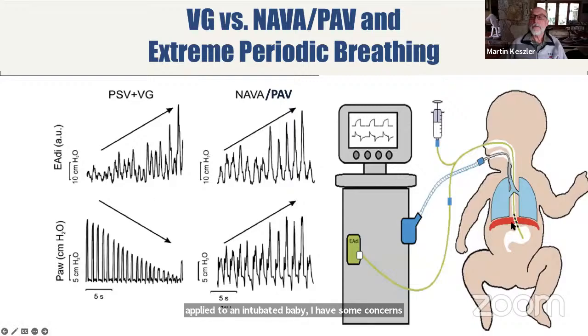So as you heard previously, basically you measure the electrical activity of the diaphragm by a specialized catheter, which by the way is pretty expensive. And that signal is multiplied by whatever level you choose, and it determines the pressure delivery by the ventilator. It is a positive feedback mechanism, meaning that if the patient's effort is very limited, there will be less pressure, and when baby breathes vigorously, it will deliver higher pressure, assuming mature respiratory control.